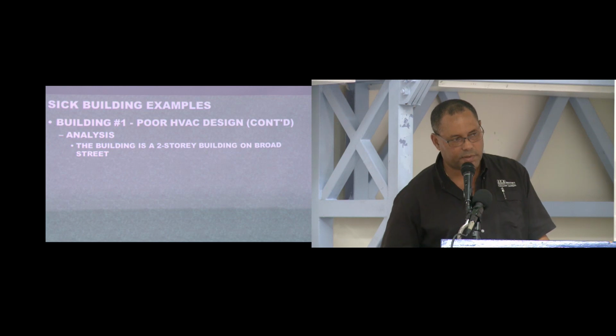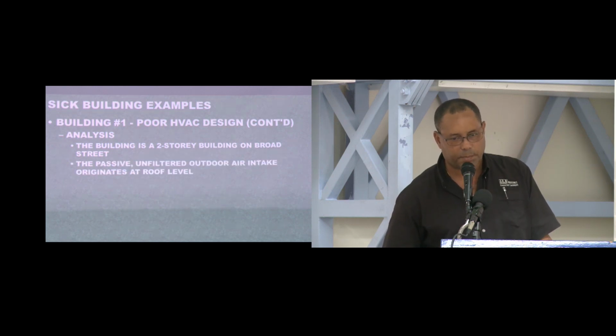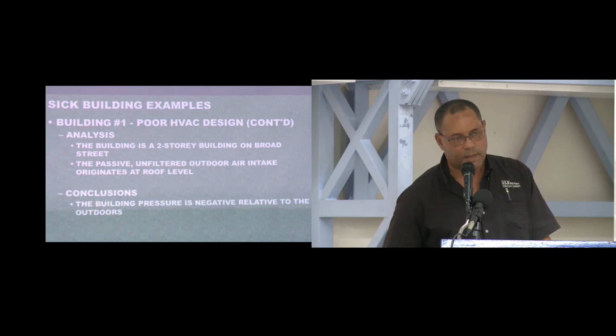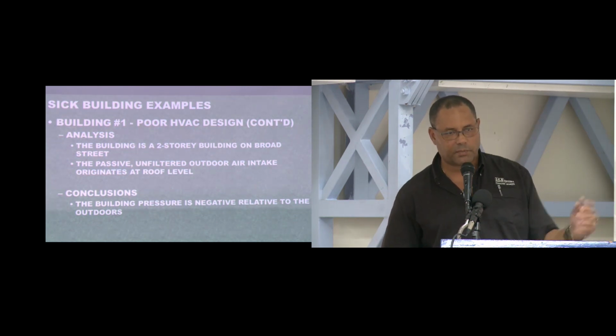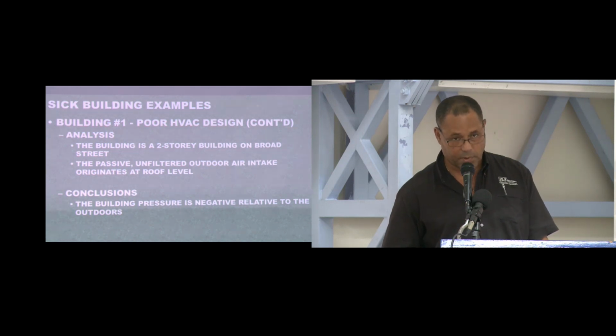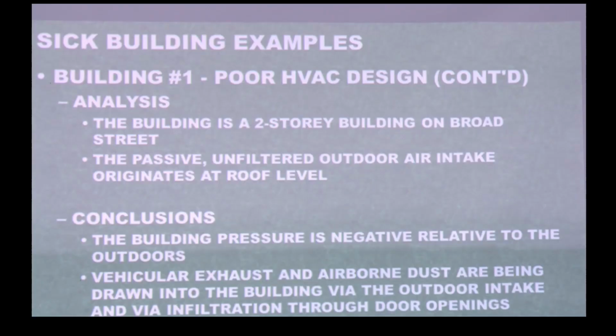So it's a two-story building on Broad Street. Passive unfiltered outdoor intake from the roof level. So the building is sucking from this duct. We have people walking in and out off of Broad Street, and we know that Broad Street is full of cars, right? Exhaust dust and fumes. What you saw there was all the dust and dirt from the vehicular exhaust and the dust in the environment being sucked into the building through the doors, through the passive unfiltered outdoor air intake, and accumulating on the inside surfaces of the duct for years.